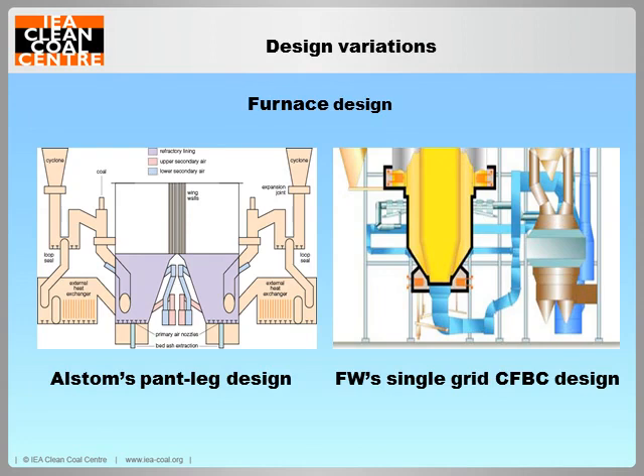The design of the furnace is key to successful and efficient operation of a CFBC boiler. The nature of CFBC combustion poses a limitation to furnace dimensions. Different approaches are taken to overcome this when scaling up. Alstom has adopted the pant-leg design, in which the lower furnace hopper is split. Each hopper is equipped with separate fuel and air feeding systems.